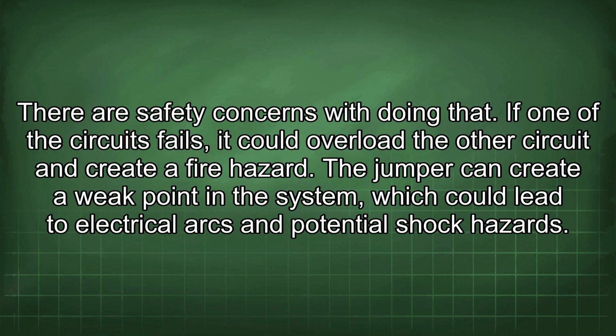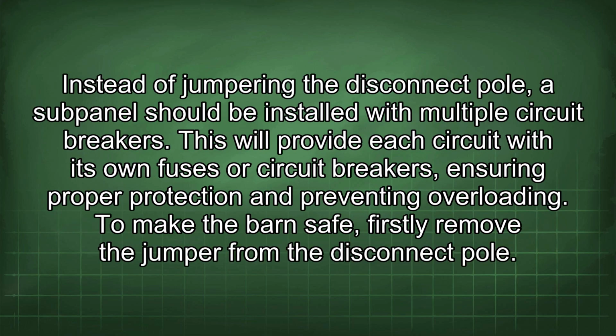There are safety concerns with doing that. If one of the circuits fails, it could overload the other circuit and create a fire hazard. The jumper can create a weak point in the system which could lead to electrical arcs and potential shock hazards. Instead of jumpering the disconnect pole, a subpanel should be installed with multiple circuit breakers. This will provide each circuit with its own fuses or circuit breakers, ensuring proper protection and preventing overloading.